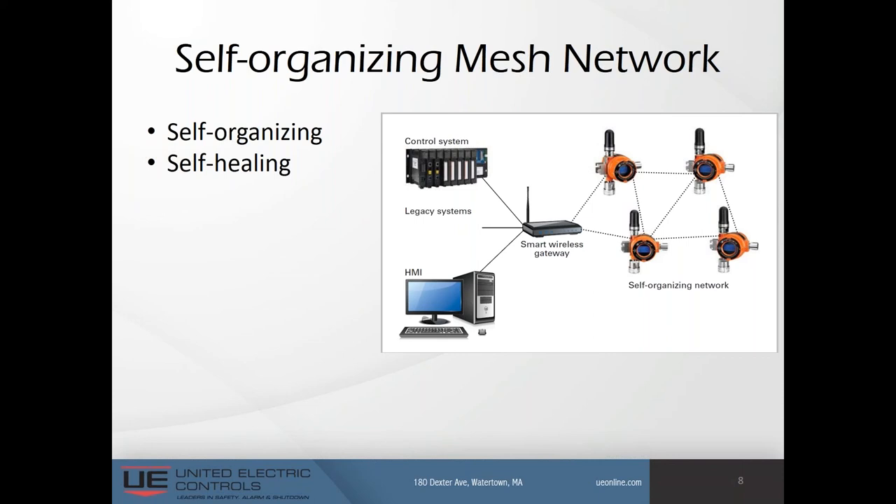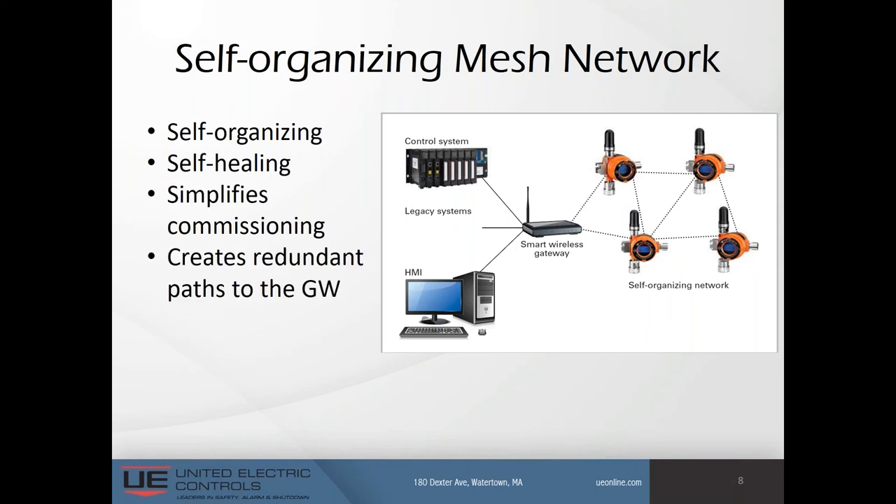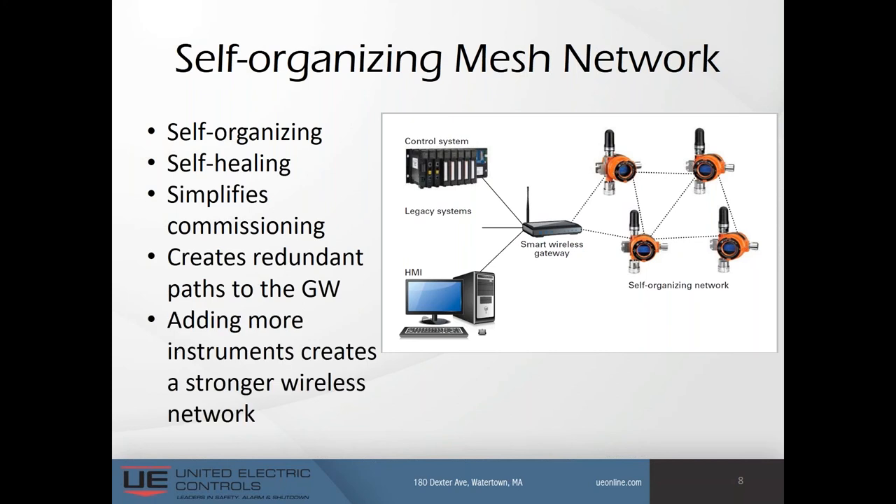To add a device to the network, you would use a field communicator — the 475 by Emerson is quite popular — to provide the network ID and the join key. The gateway will then detect the device and add it to the network, automatically optimizing wireless network connections for obstructions, distance, and signal strength. This simplifies the commissioning process, creates redundant paths to the gateway, and adding more instruments creates a stronger wireless network.